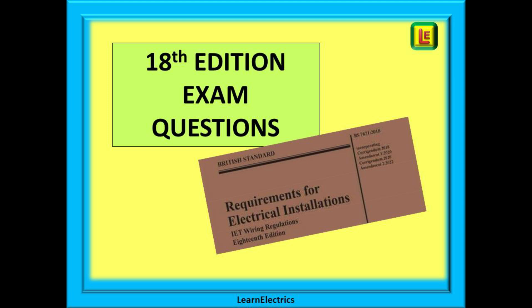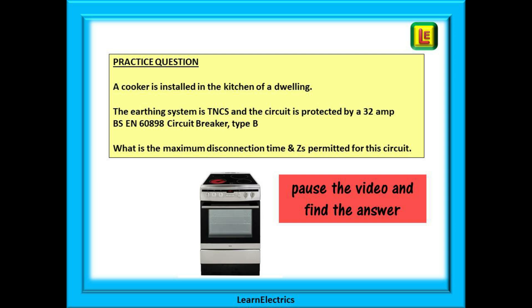Let's have a look now at some exam type questions. This question is related to ZS and disconnection times. A cooker is installed in the kitchen of a dwelling. The earthing system is TNCS and the circuit is protected by a 32 amp BS EN 60898 circuit breaker type B. The question is, what is the maximum permitted disconnection time and the maximum permitted ZS for this circuit? Pause the video and attempt the question.